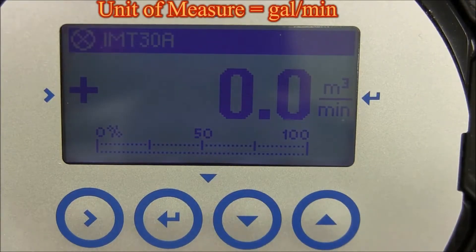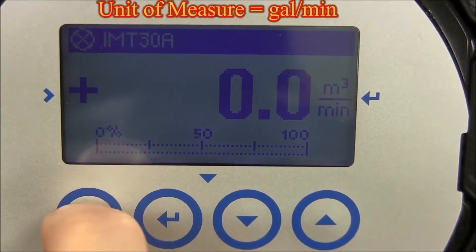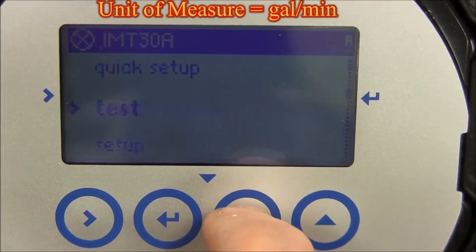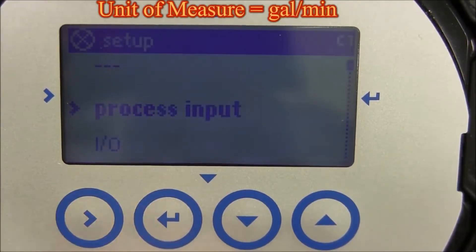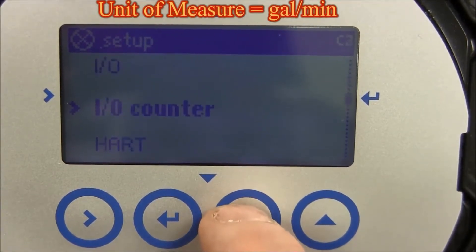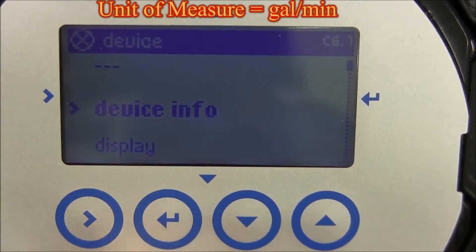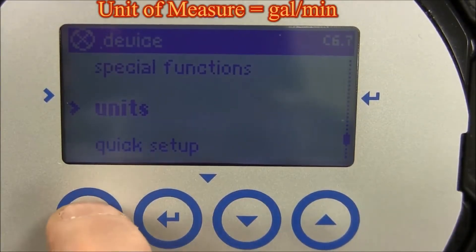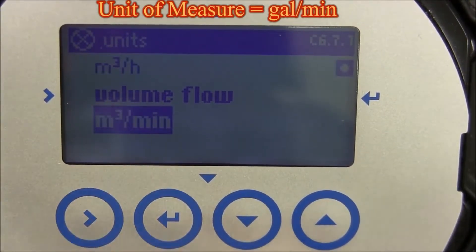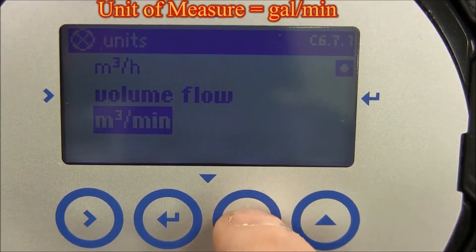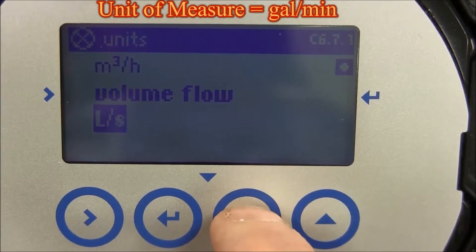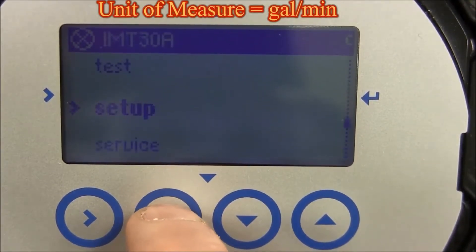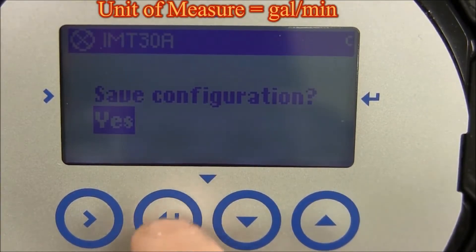To select gallons per minute as your unit of measure, press and hold the right arrow for three seconds, then let go. Press the down arrow until you see setup, then press the right arrow. Press up or down until you see device, then press the right arrow. Press up or down until you see units, then press the right arrow. Press the right arrow to go into volume flow and go up or down until you see gallons per minute. Press the right arrow, then press the enter key. Continue to press the enter key until you see save configuration. With yes highlighted, press the enter key to save your selection.